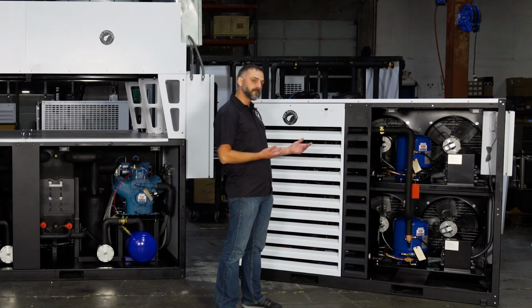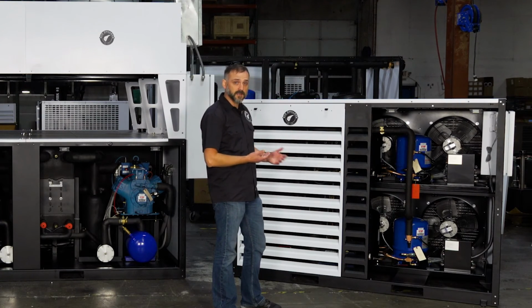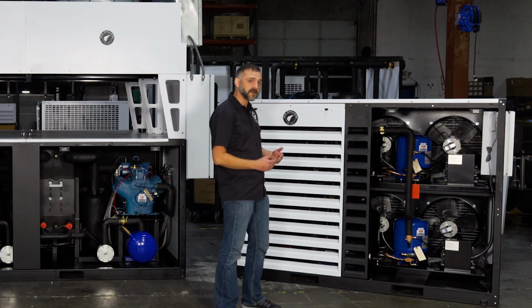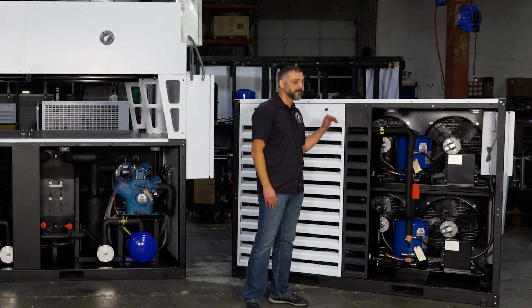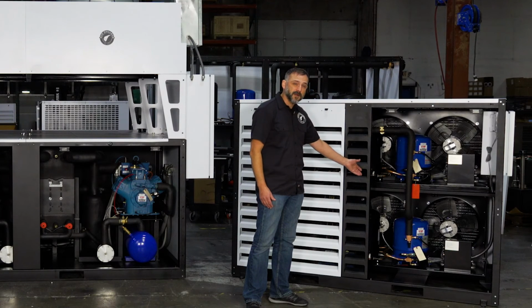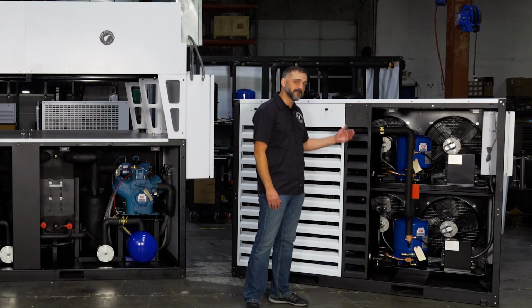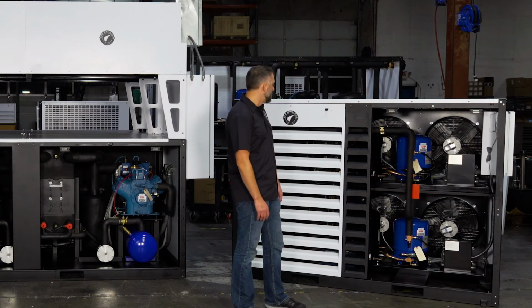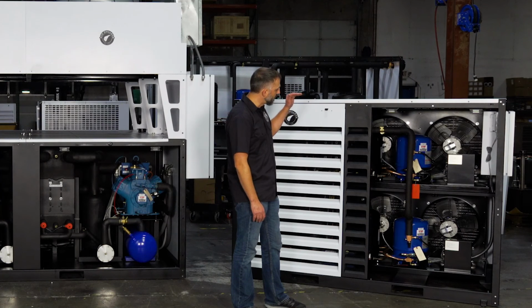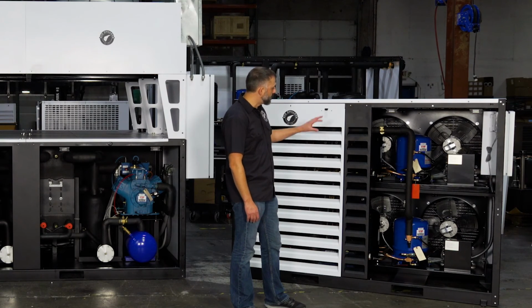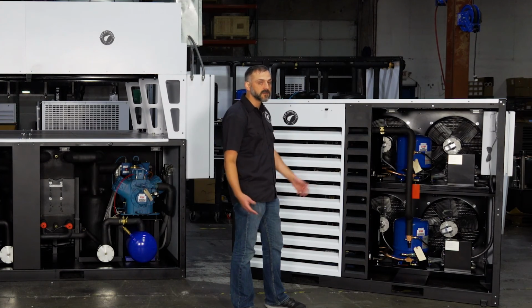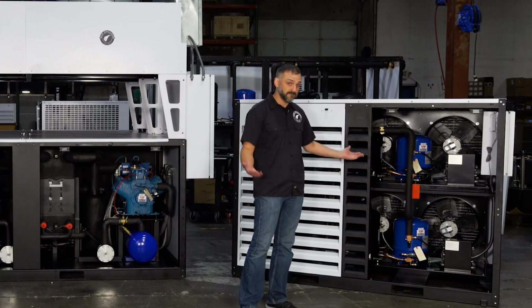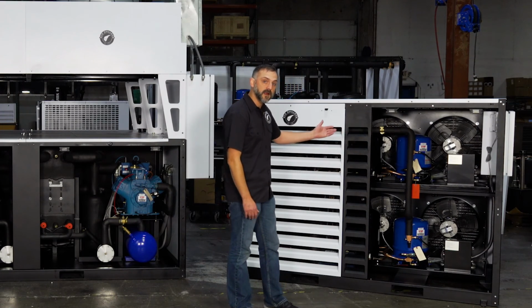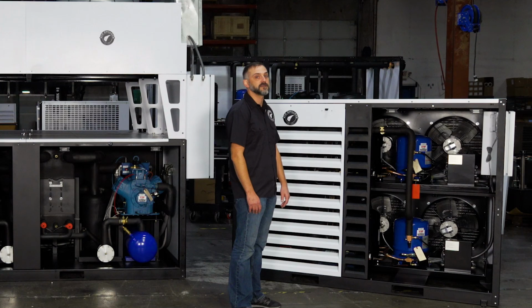If you're smaller and you have some expansion plans, you're gonna get a chiller that you can grow into and do it efficiently. You're not gonna burn a bunch of energy. If you start off with a production that is low, you're only gonna run one of these compressors at any given time. And if it's summertime and you've stepped up production, brought in some more tanks, the additional circuit will kick on and cover your demand. So it's a great chiller package. They will cycle on and off as needed. Both circuits will have equal runtime over the life of the chiller, and then redundancy is huge. In the unlikely event a circuit goes down, the other one's automatically running, so you're not dead in the water, and that's huge in production. That is huge when you have beer in your tanks.